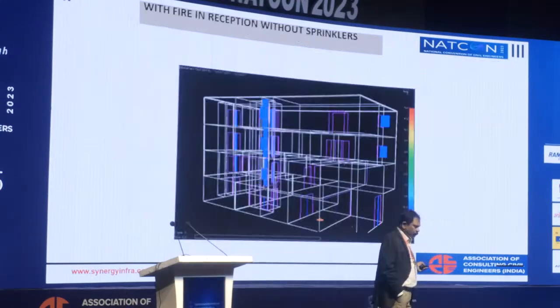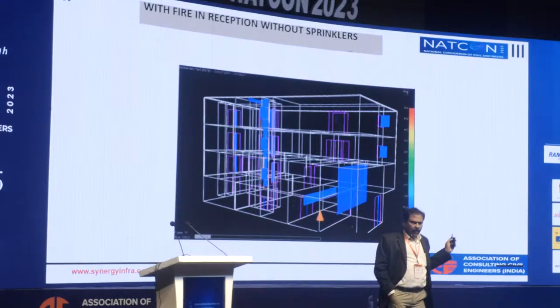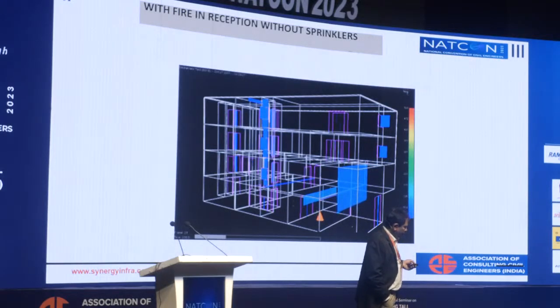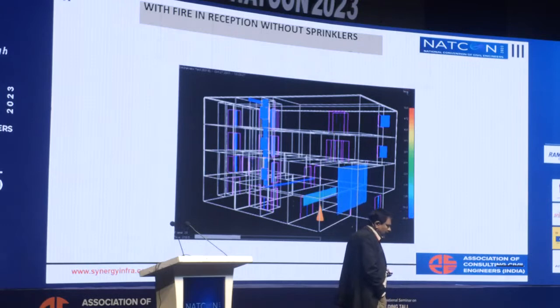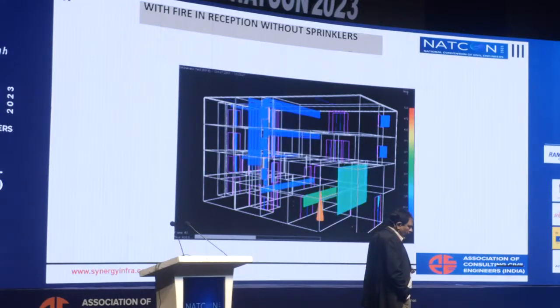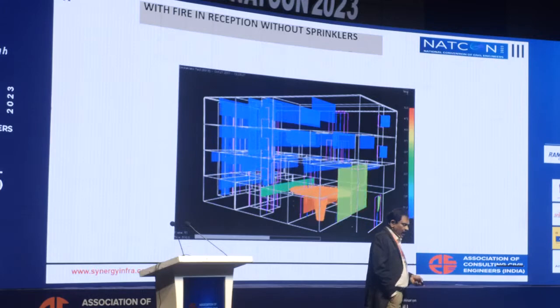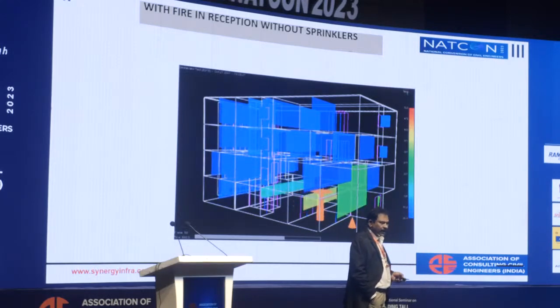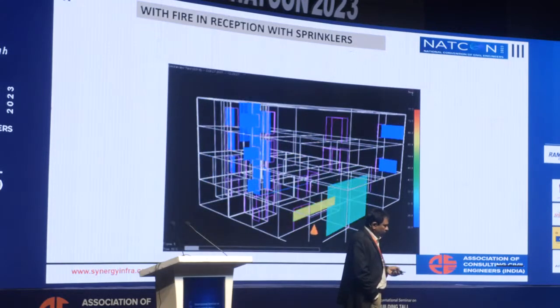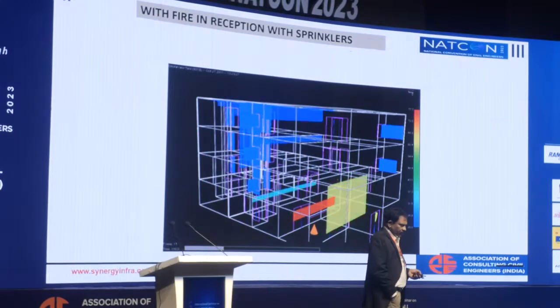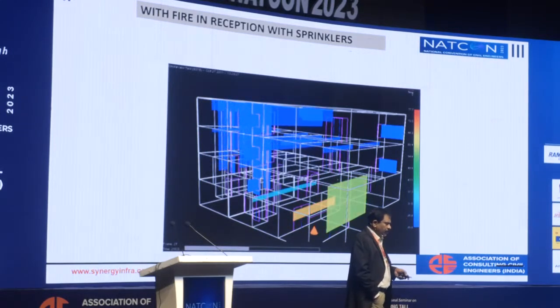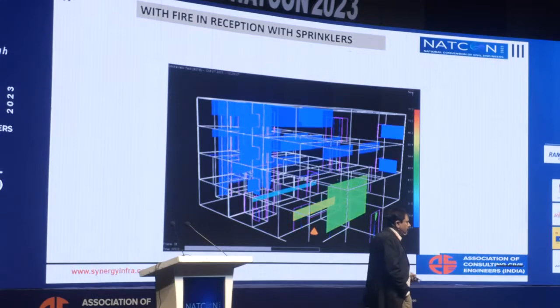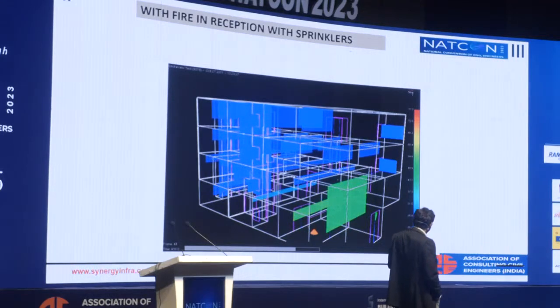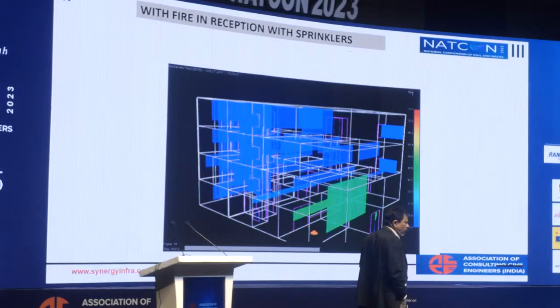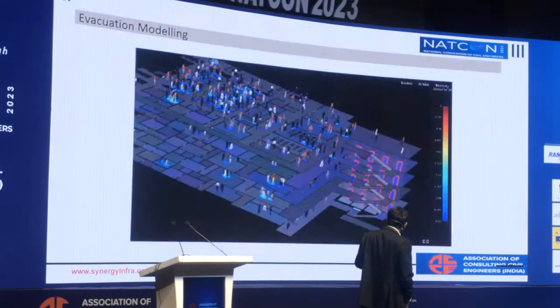This is a small fire modeling we did using CFAST, without sprinklers, where temperatures can go as high as 250 to 300 degrees, and at lower levels almost up to 500 degrees. For the same building with sprinklers protected, you can see the temperature brought down immediately as soon as the sprinklers operate. This was done for a small building with around 30 rooms as a case study.